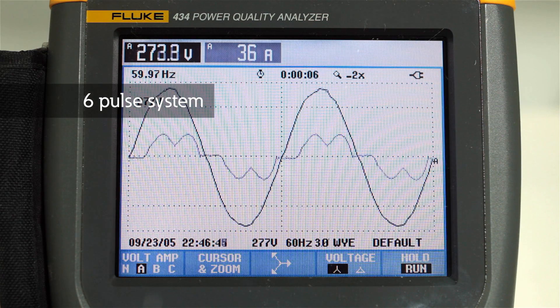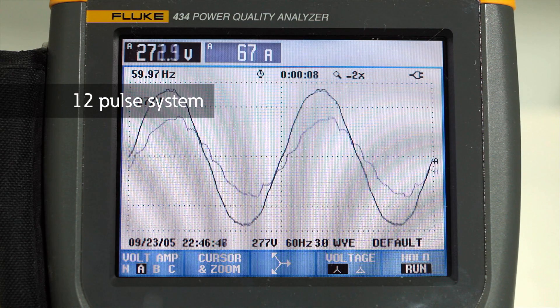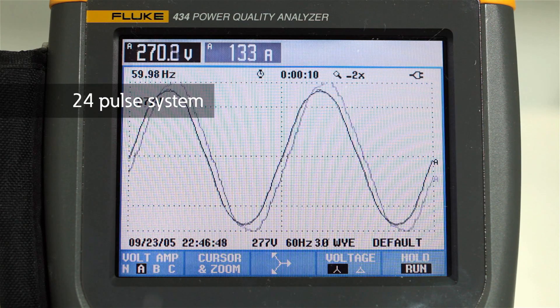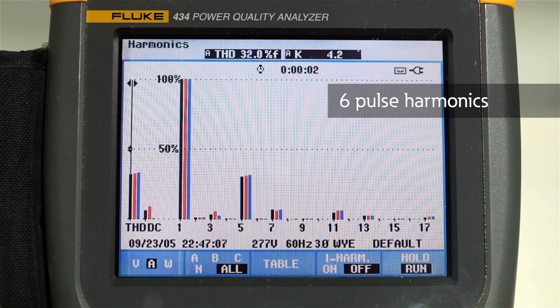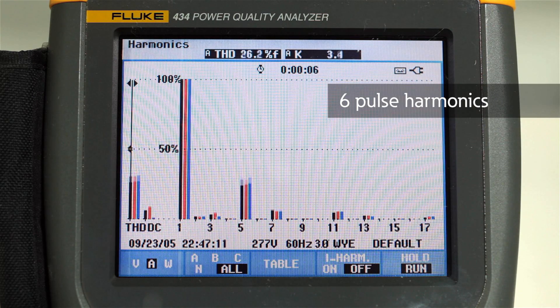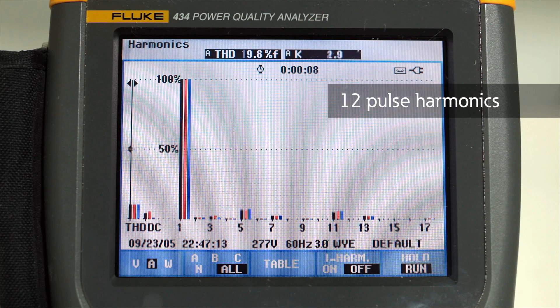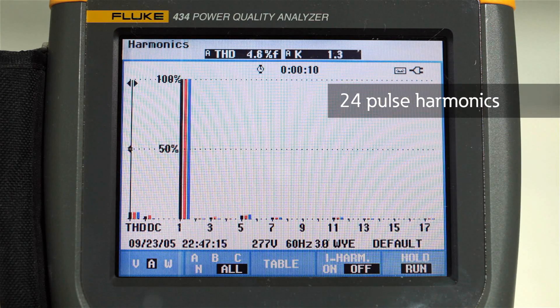For example, phase-shifting transformers can transition a system of 6-pulse drives to reduce the harmonic distortion in the current and voltage. These waveforms show the transition of a 6-pulse system to a 12-pulse system to a 24-pulse system.